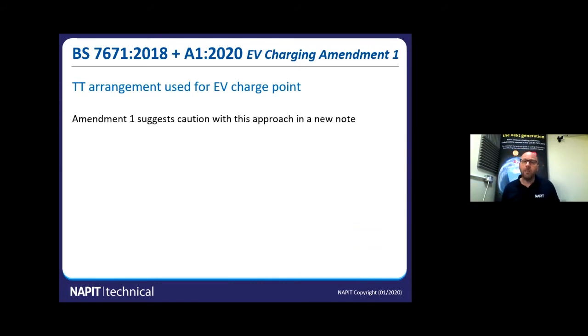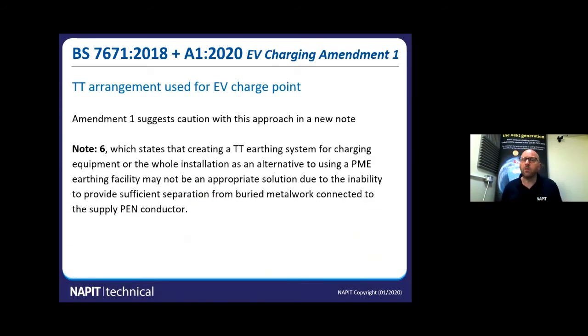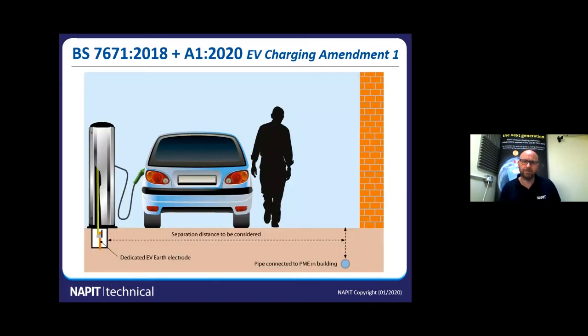However, Amendment 1 has introduced a new note, Note 6, which says that creating a TT system may not be suitable. It may not be because of the buried metalwork. It is an issue that we're talking about at committee level, and what we're talking about is voltage transfer. So let's have a little look at that.